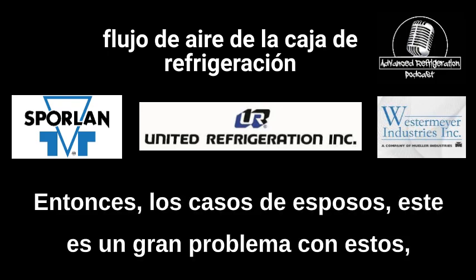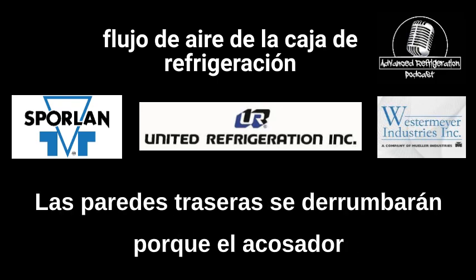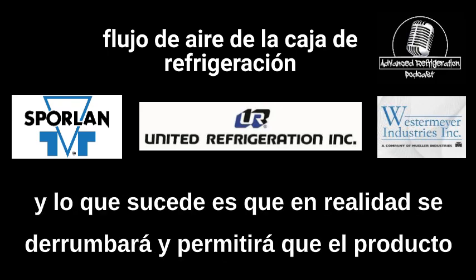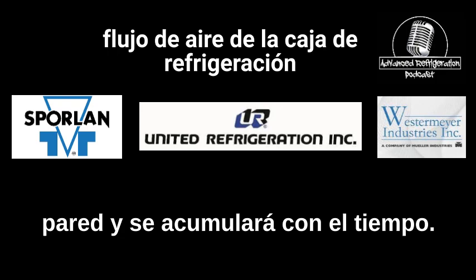So the Hussmann cases, this is a huge problem with these, is the back walls on the 4-foot coil sections. The back walls will kind of cave in, because the stocker just shoves that product in there. And what happens is it'll cave in and allow product to fall on top of the evaporator coil that's in the back wall, and it'll build up over time.